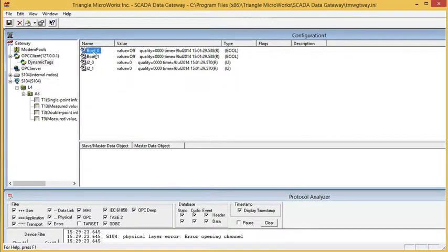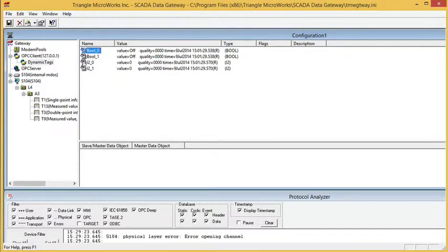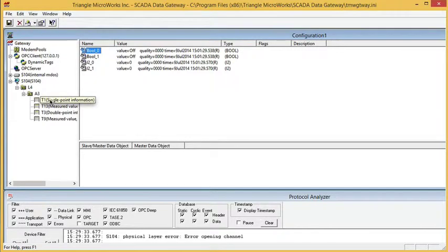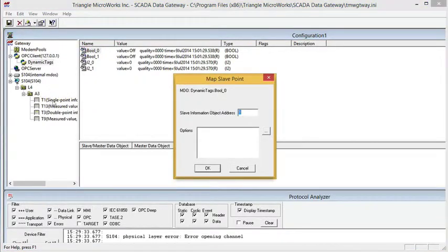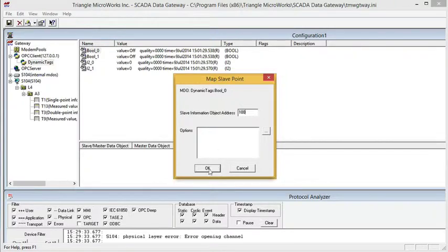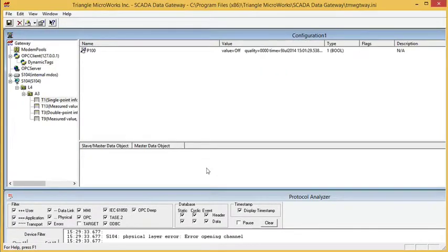The only way to create data in a slave component is by mapping a point from a master component. So in this case, we're going to map from the OPC client to the slave. I'm just going to make my single point IOA 100.